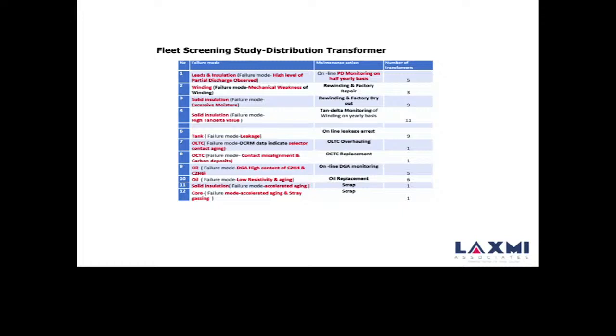If we classify using FMEA, we have problems on the lead and insulation side where we observe high levels of partial discharge. We have winding failures because of mechanical weakness. We have solid insulation with excessive moisture problems. We have high tan-delta issues, meaning aging of the insulation is on the higher side.